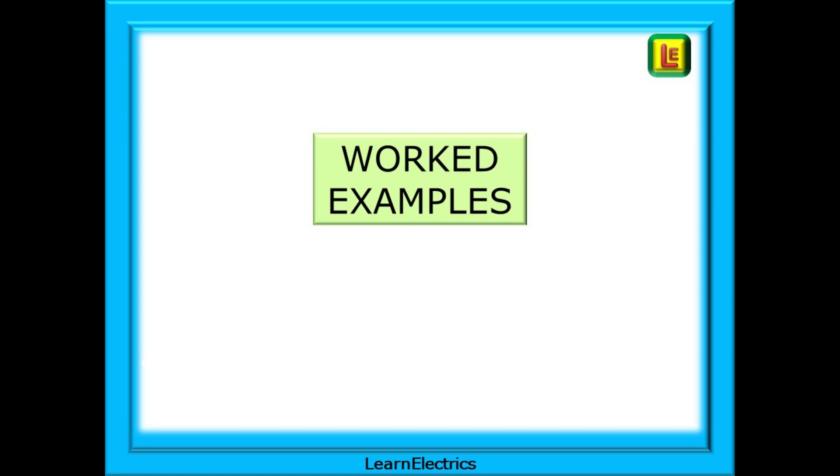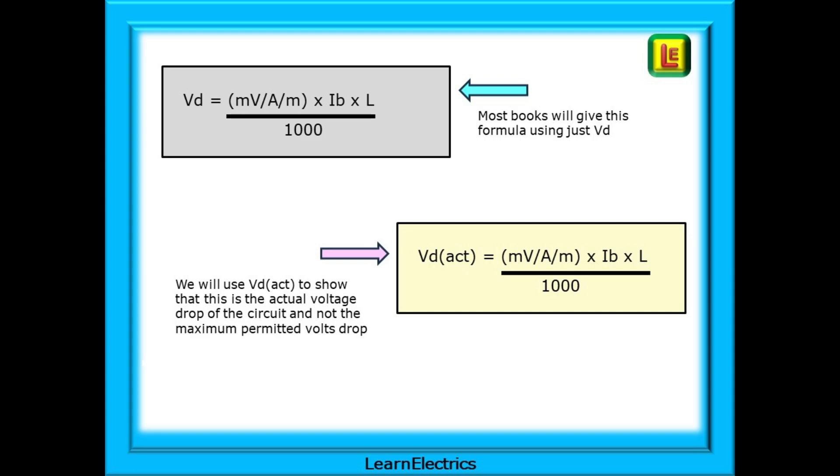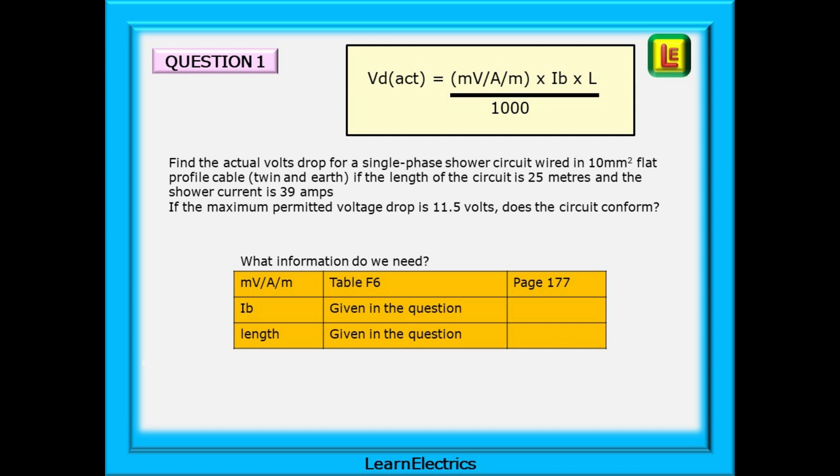Let's have some worked examples now to reinforce our understanding. Most books will give this formula using just VD but it's easy to become confused. Are we dealing with the actual volts drop or the maximum volts drop? As I mentioned before, I avoid this by using VD(act) to show that this is the actual volts drop of the circuit and not the maximum permitted volts drop. Question 1 asks us to find the actual volts drop for a single phase shower circuit wired in 10mm flat profile cable or twin and earth. If the length of the circuit is 25 meters and the shower current is 39 amps, if the maximum permitted voltage drop is 11.5 volts, does the circuit conform to regulations?